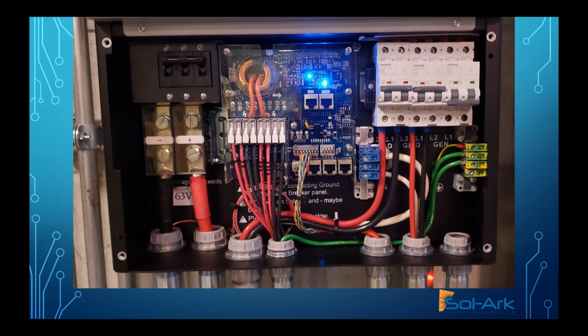The little rainbow colored wires going into the pinouts there, those are going to be sensors and communication. So that's where we're going to land the generator auto start. That's where we're going to bring in rapid shutdown, etc. So that's where that is. You can see the grid breakers populated, the load breakers populated. This is kind of a nice shot of the installed unit.